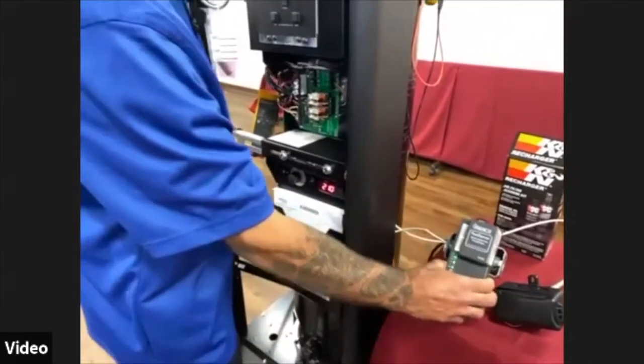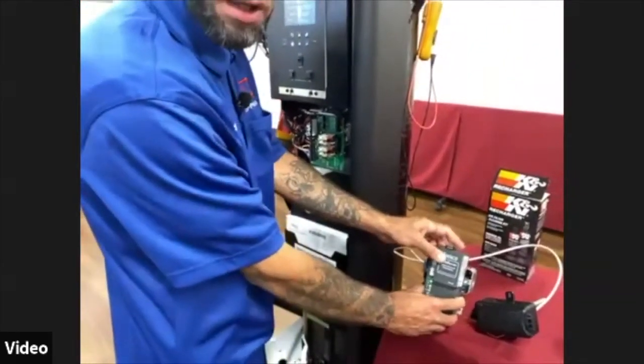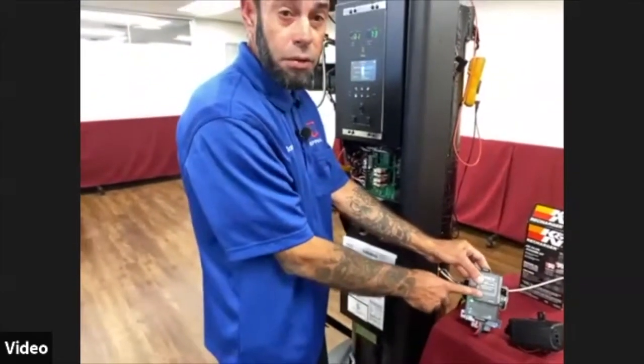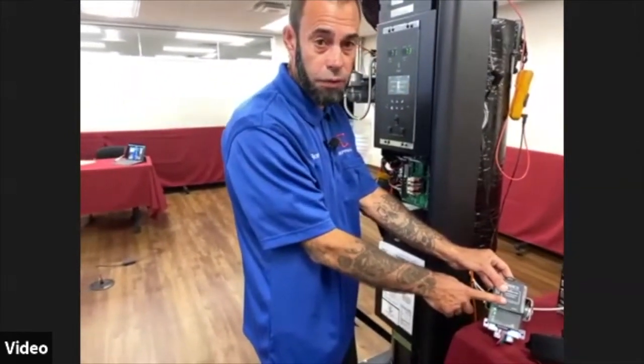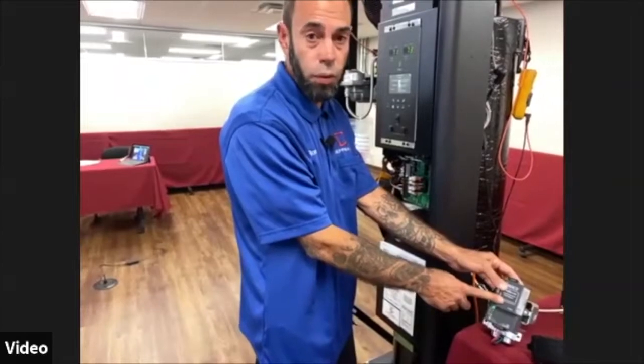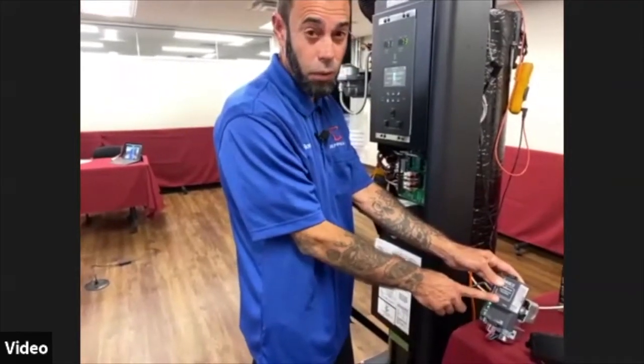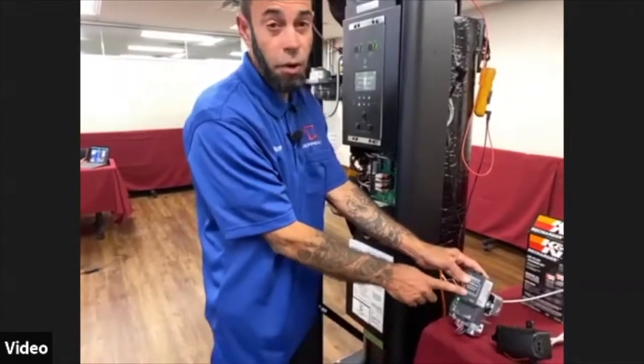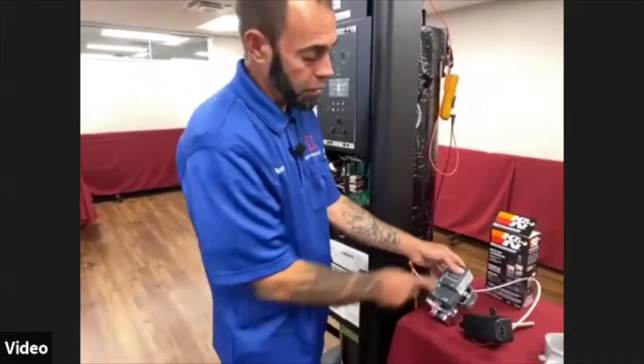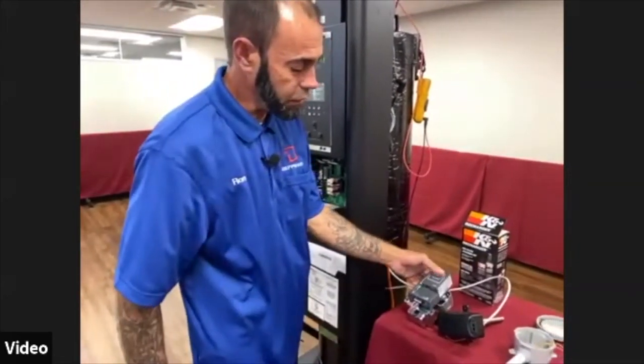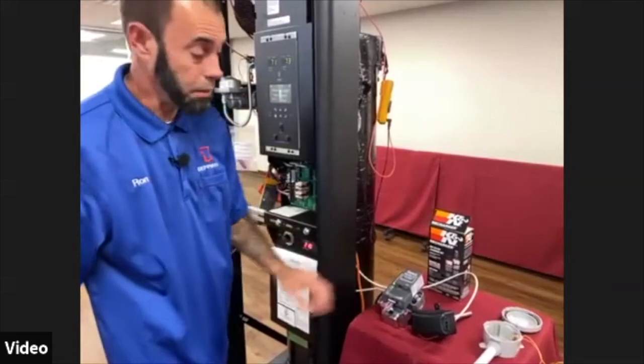Also, one other thing to note with the FieldServer, don't power this off of 24 volts from the boiler. We would really like you to have a separate 24-volt power source to this. Most of the guys will mount this into their building management panel anyway, and bring their RS-485 communication back to it.